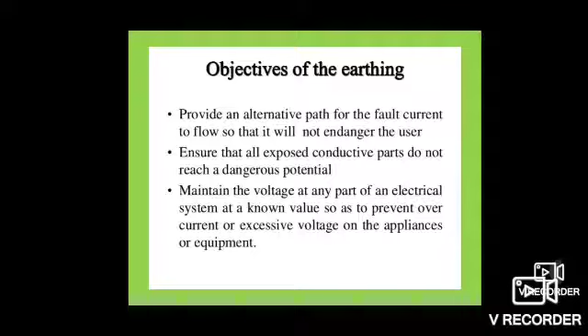Let us see the objectives of earthing. It provides an alternative path for the fault current to flow so that it will not endanger the user. Ensure that all exposed conductive parts do not reach a dangerous potential. Maintain the voltage at any part of an electrical system at a known value so as to prevent overcurrent or excessive voltage on the appliances or equipment.